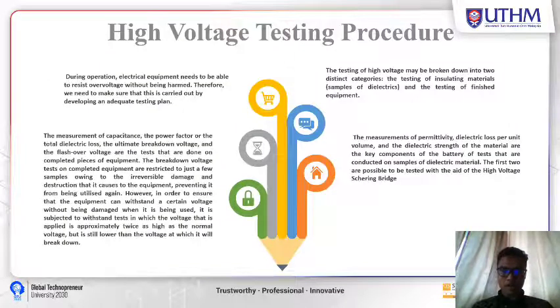Next is the high voltage testing procedure. Before we do the experiment, we need to know the procedure of testing. During operation, electrical equipment needs to be able to resist overvoltage without being harmed. Therefore, we need to make sure that this is carried out by developing an adequate testing plan. The testing of high voltage may be broken down into two distinct categories: the testing of insulation material samples of the dielectric, and the testing of finished equipment.